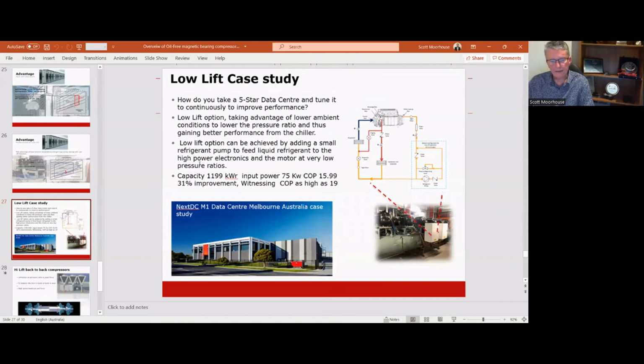And there was a case, a data center done in Melbourne, where there were some existing chillers running, and we looked at the performance of these machines. Then, as an aftermarket product, a low lift system was fitted to these machines. We took a 5-star data center and had significant improvements of up to 30% when running in low ambient. There were about 12 chillers with about 1200 kilowatts of refrigeration, and we went to COPs as high as 19 on that application. So even though the data center was already a 5-star data center, we improved the chiller performance by 30% in certain ambient conditions.